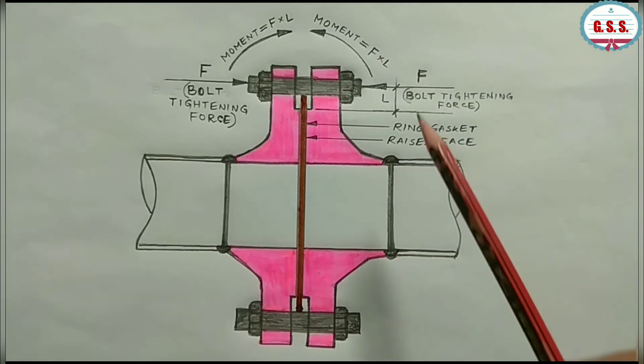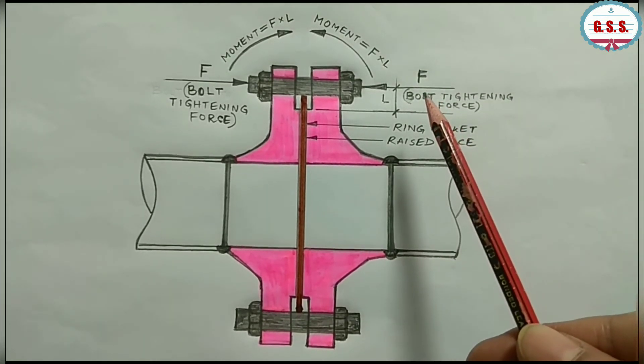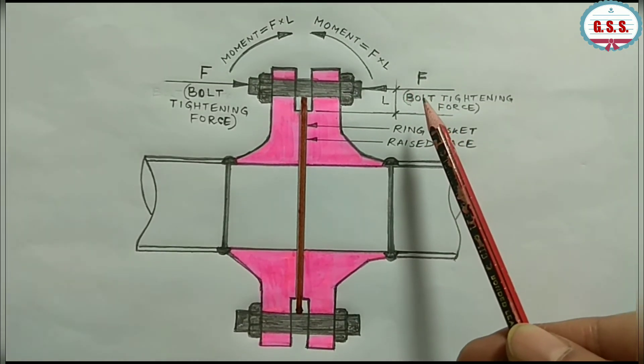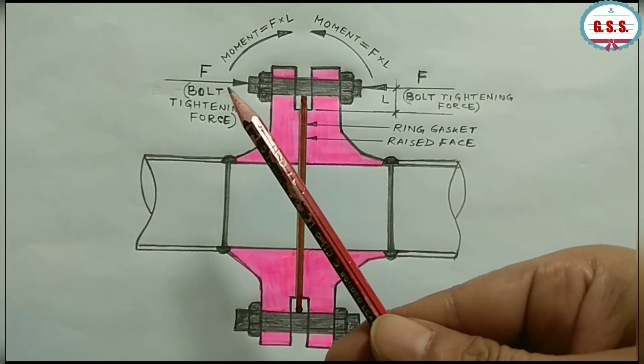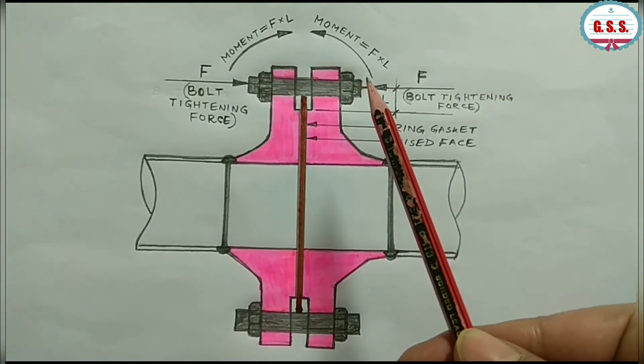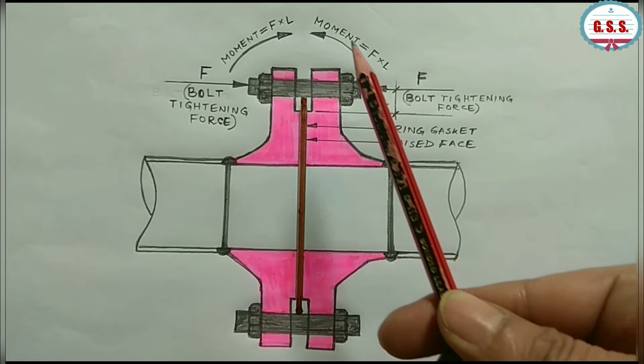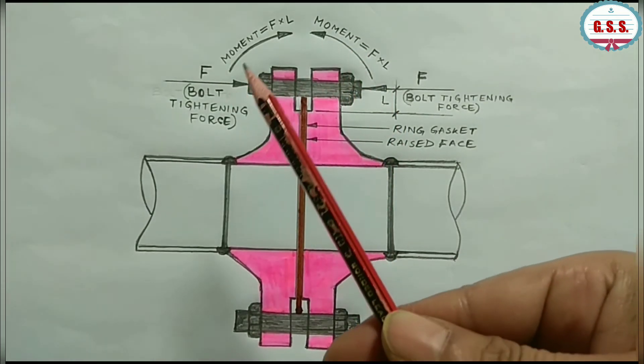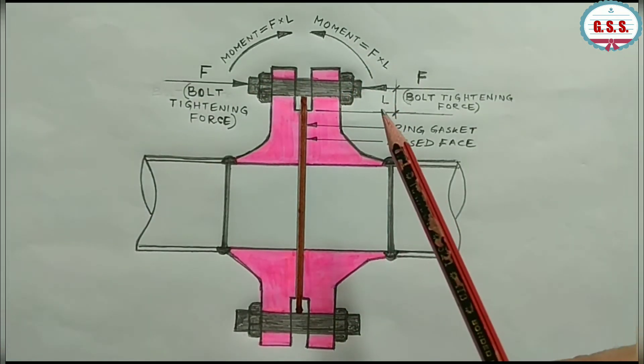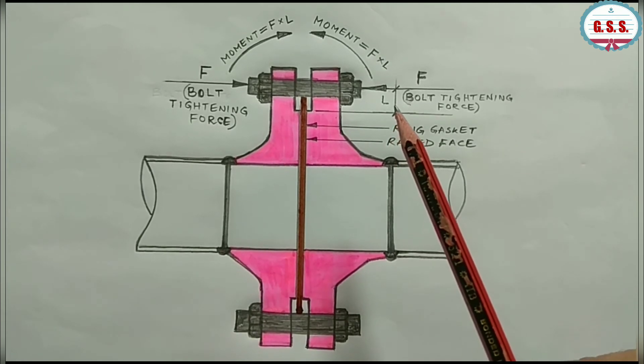If flange bolt tightening load is F, then the gasket is compressed by this force from both sides of the flange. Additionally, a moment is created which is equal to this force F times the distance from bolt circle to raised face outer diameter.